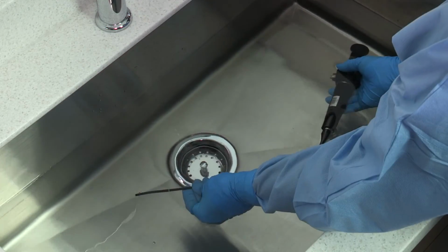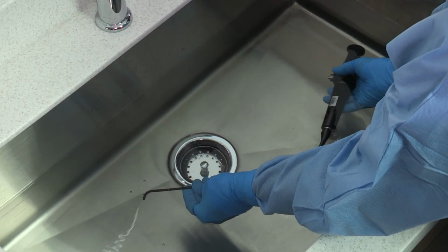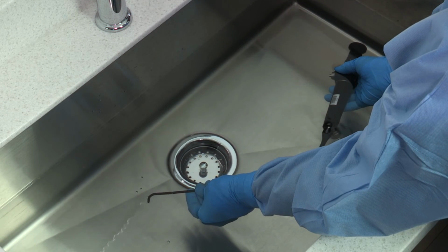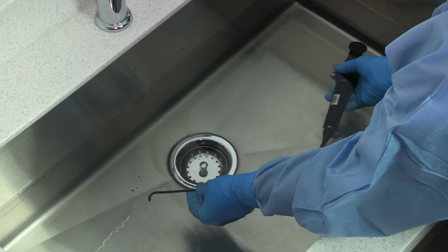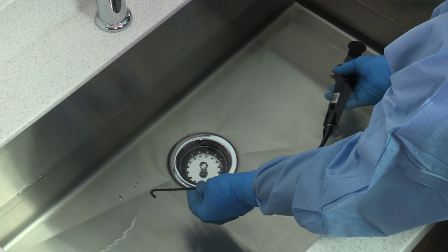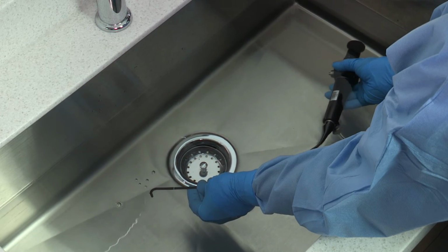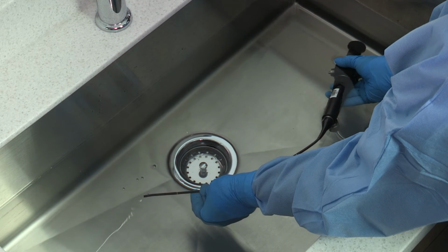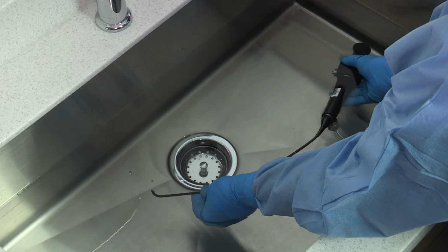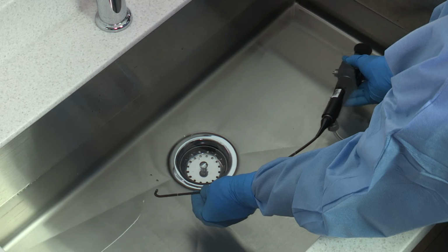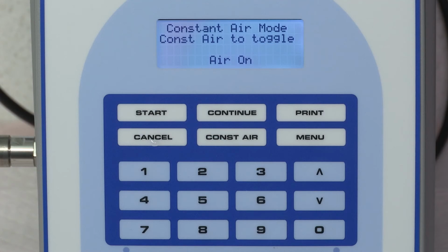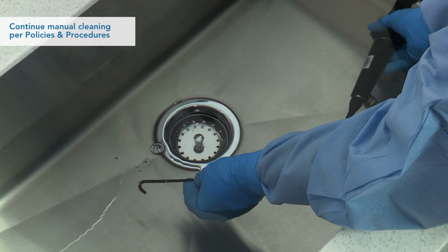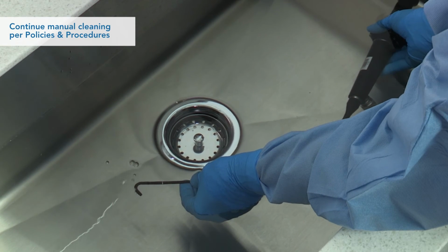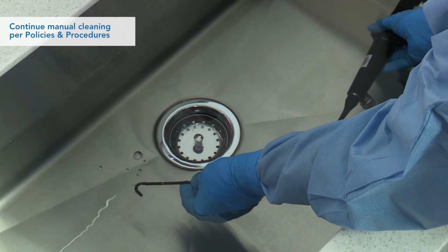Take your time and carefully look for air bubble leaks, making note of any locations. To manually clean an endoscope with a leak, a continuous airflow must be maintained during the entire cleaning process. The continuous airflow creates a constant internal endoscope pressure that prevents fluid from invading through the leak. Therefore, leave the constant air on while manually cleaning the endoscope. Manually clean the endoscope according to your policy and procedure for handling endoscopes with leaks, prior to sending the endoscope for repair.